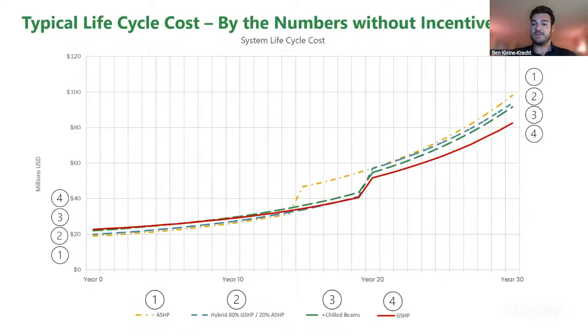With the chilled beams, you'd have to replace the 6-pipe water-to-water unit at some point, along with the compressors associated with that. Over time, the overall goal here is that first cost is what it is, but over the course of 30 years, it works out so that the geothermal option has the lowest life cycle cost.